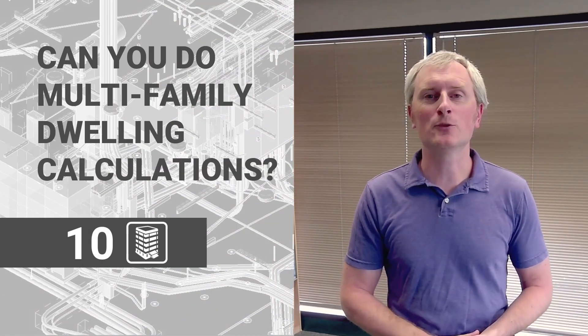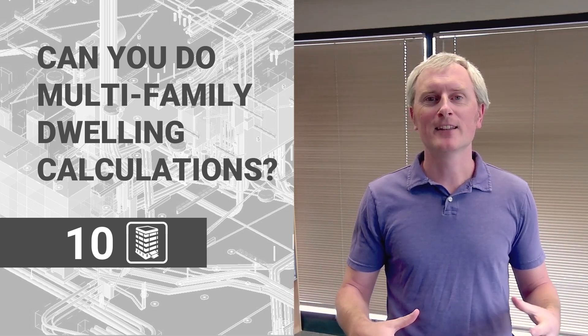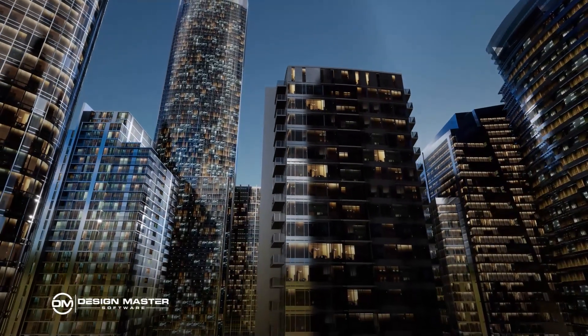Level ten I'm calling multi-family dwelling calculations, but it's really a whole host of higher-level calculations. I'm using multi-family dwellings as an example of the type of calculations you're looking for in a true level ten BIM software. This is where you take feeder and service load calculations into the deep nitty-gritty of the NEC — things like the optional parts of NEC 220. If a BIM package includes them, that indicates a depth of calculation that's going to handle most of what you'll need for your design purposes.